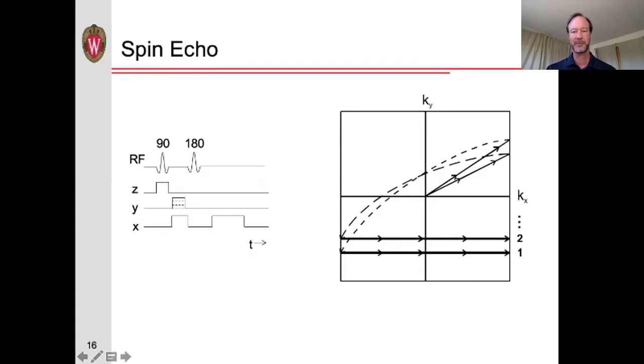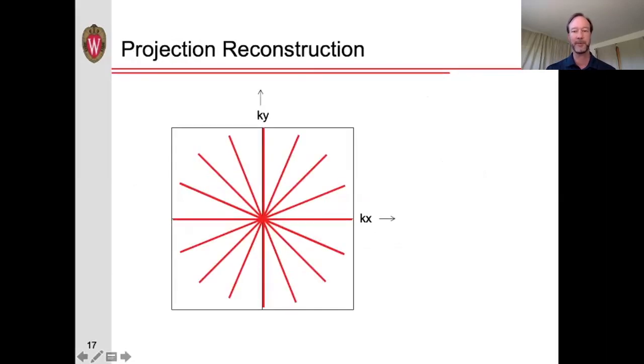Now let's look at some other ways we might sample k-space. One would be projection reconstruction — instead of acquiring different phase encoding steps, we rotate the direction of the gradients and acquire different spokes of radial projections. We can then do either a radon transform or re-grid the data in order to create our actual image.